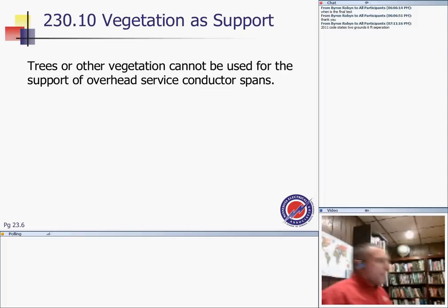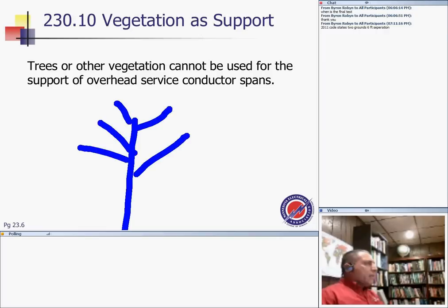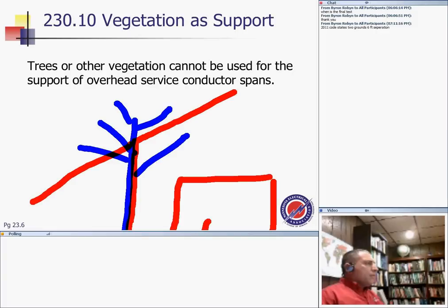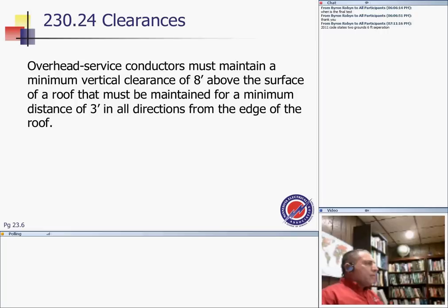Vegetation and support. You have a nice pine tree sitting over here, thinking that you can put your power lines in it. You are dreaming. And some of you might say, "Not Chad, I can use my power line, tie it from here, go from here, and by the way, bring a wire all the way underground here and feed it into the building." That's wishful thinking. You can't use vegetation. Trees cannot be used for support of overhead service conductors. So that's a few things for the service entrance conductors. As a matter of fact, you can't use trees for feeders also. The same way too, you have to use a pole, especially side poles and so forth.